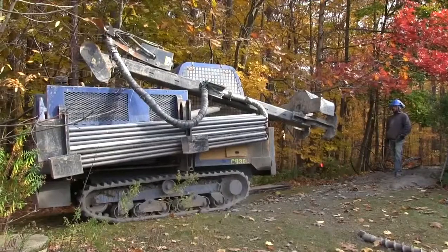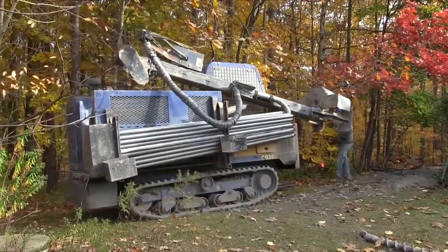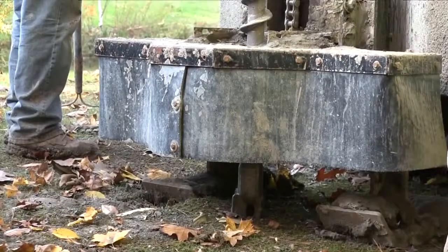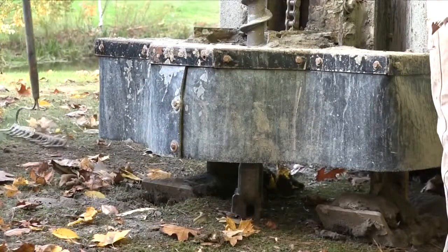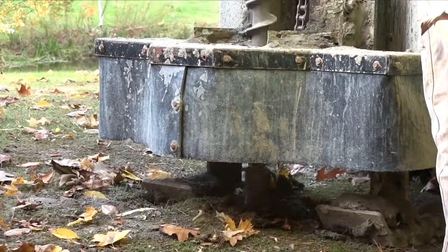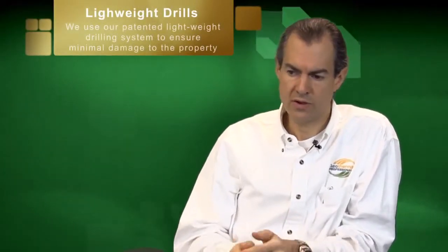Shallow depth would be 8 feet or shallower. The vertical drilling we can take onto a very small lot without doing damage to the property. Smallest lot we've been in has been in the city of Lakewood. A vertical drill can traverse a driveway, a sidewalk, or a lawn without doing damage. A vertical drill can get through rock, it can get through gravel, it can get through clay. A horizontal directional drill we typically take on to properties that have an acre or more, where we can traverse underneath a wooded area or a field.